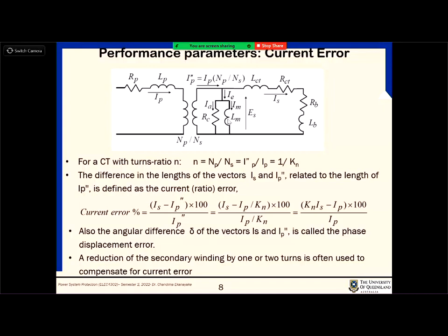Now, if you look at the real transformer, you don't have any excitation branch, you can't see it, right? This is an equivalent model. Those current differences happen because of the flux, the losses and a lot of other things. But when you are looking at the equivalent circuit, it's easier to understand. So the primary current is here, and the secondary current is here, which is the current measured by the relay. But the ratio between primary and secondary is not exactly equal to the turns ratio. Because of that, some error is introduced. So we will look at mathematically how we can represent it.